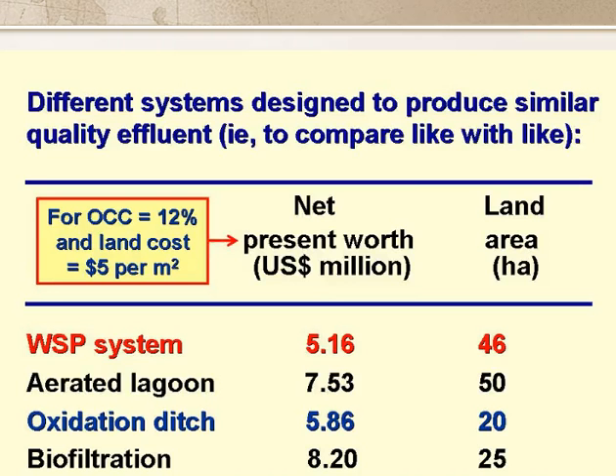Arthur designed his four systems to produce effluents which were closely similar. So the aerated lagoon system was designed with maturation ponds, and the oxidation ditch and biofilters were followed by effluent chlorination, in order to get the faecal coliform count the same as that produced by ponds — that is, to below 10,000 per 100 ml.